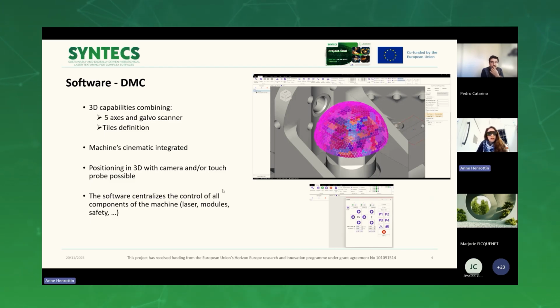We have also integrated and used DMC software to process the 3D cuts. Here's a picture of how we do it on the cut of the implant. We have a 3D capability by synchronizing the 5 axes with the 2 galvano scanner axes, and we produce little tiles to process each tile by itself. Inside this software we also have the whole machine simulated on the screen. We also have the possibility to position in 3D thanks to a camera or touch probe. And at the end, with this software, we can control all the machines, so we can start the laser.